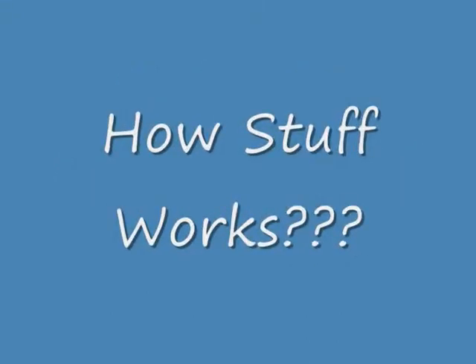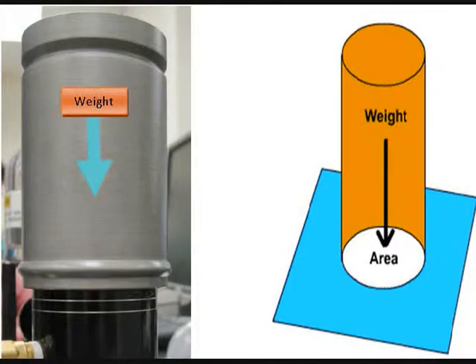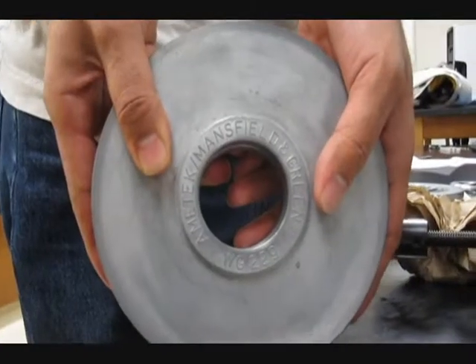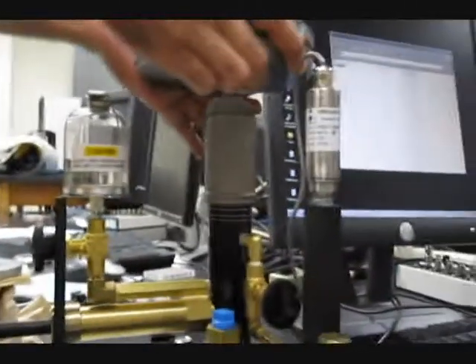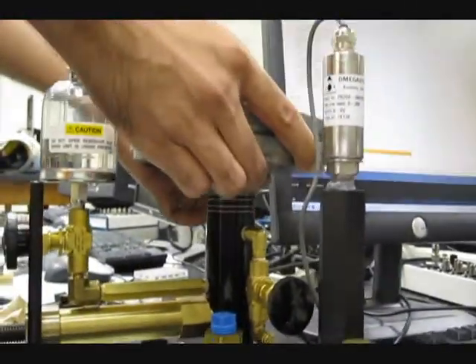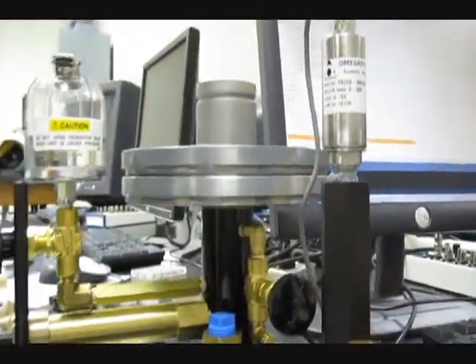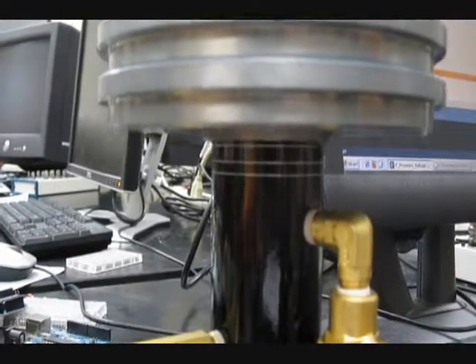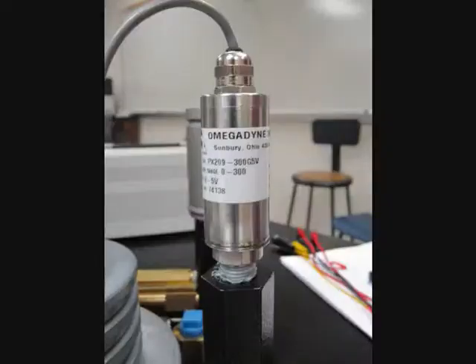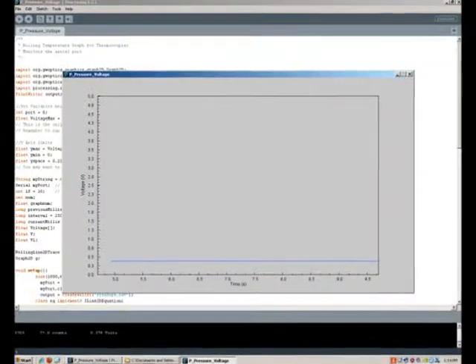How stuff works: in this lab, we will use a deadweight tester to generate and record a pressure difference by applying a force over a given area to a fluid. By applying different amounts of mass to the piston, which floats between the horizontal lines on the deadweight tester, force is applied over a given area and transferred through the fluid. A pressure transducer then records this change in pressure and outputs a signal, which is sent to an Arduino to be recorded on a computer.